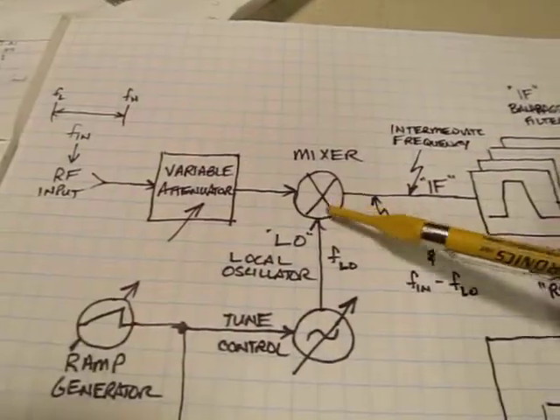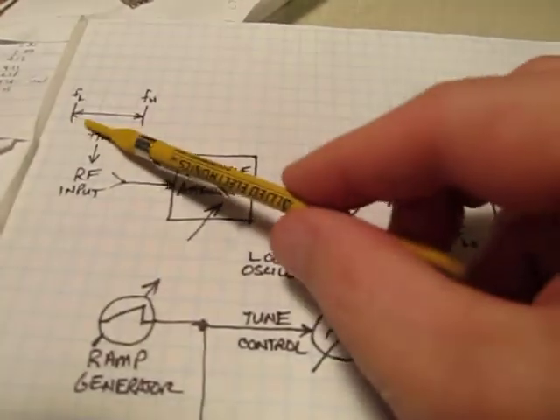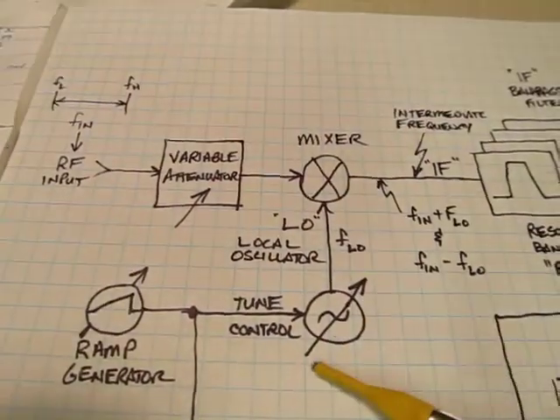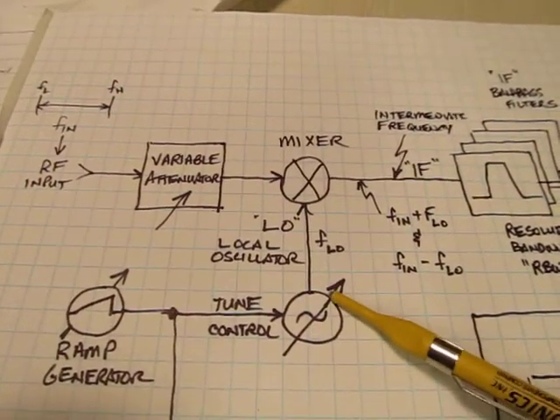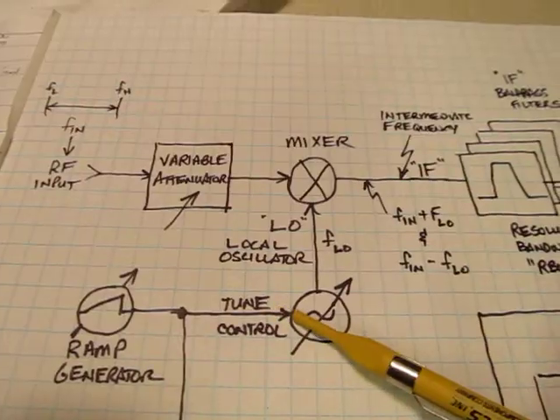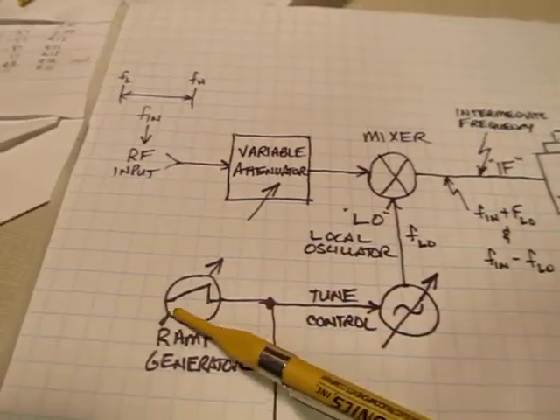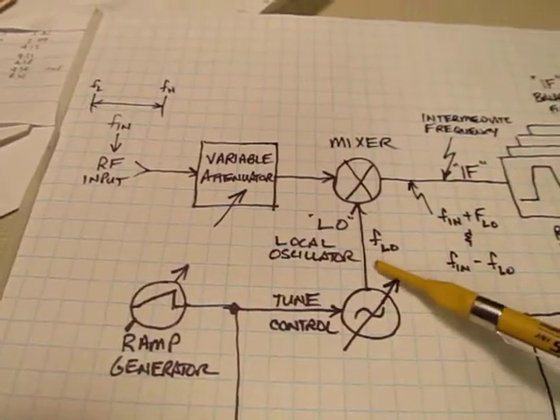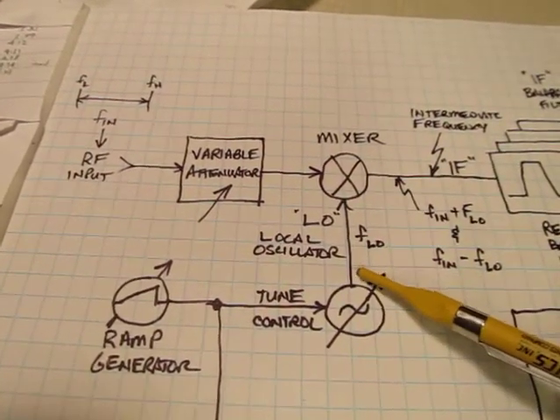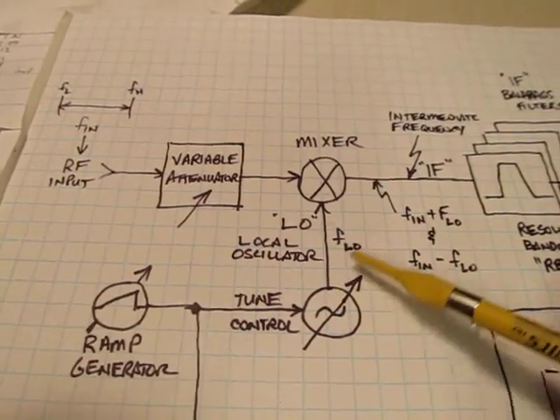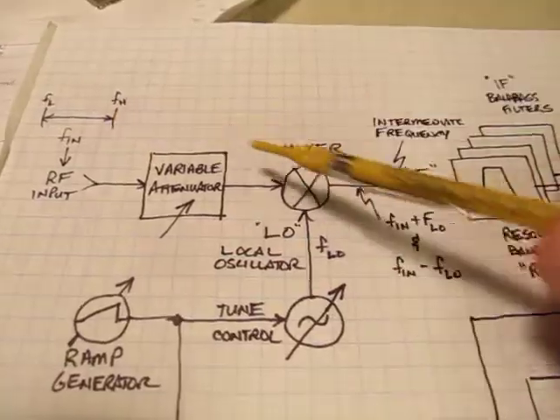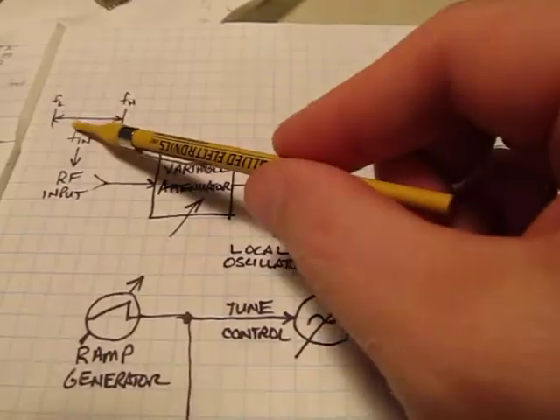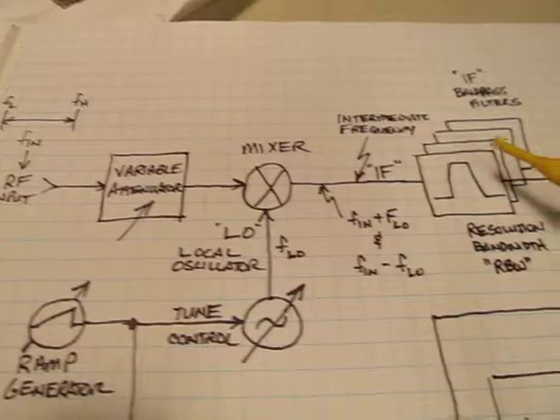And typically what we're doing is we're trying to sweep across this given frequency range. So the way we do that is by making this local oscillator adjustable. Typically it's a voltage controlled oscillator or VCO. So it'll have a tune voltage control input. And if we drive that tune voltage with a ramp generator, it will basically cause FLO to sweep from some low frequency to some high frequency, which is going to essentially sweep across this input frequency range and make these signals that are appearing here land in the IF.